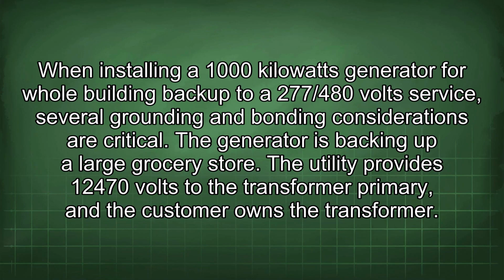When installing a 1000 kilowatts generator for whole building backup to a 277/480 volt service, several grounding and bonding considerations are critical. The generator is backing up a large grocery store. The utility provides 12,470 volts to the transformer primary, and the customer owns the transformer.